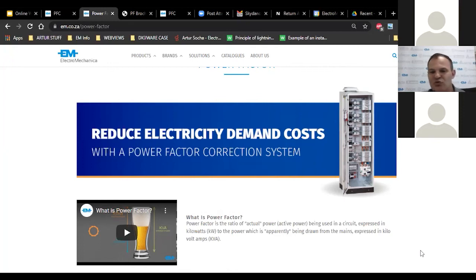So it's quite a one. You will need to have some sort of power quality logger established at the first point of coupling. Is it bad there? Where are we sitting, and which load is creating the biggest problem? Because you might just need to sort that specific load out. Maybe you've got a chiller plant, and that in itself is creating an internal problem on harmonics. So it is a little bit of investigation. You do need the tool to do it. So there's not an answer for everything. You'd have to do a bit of measurement to see what is worst and what is contributing the most.